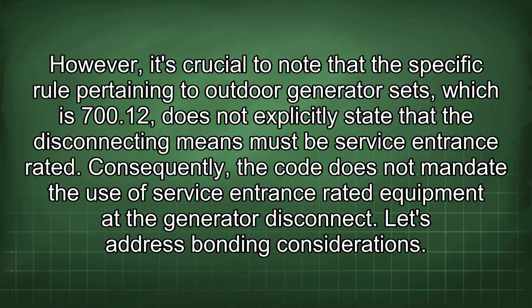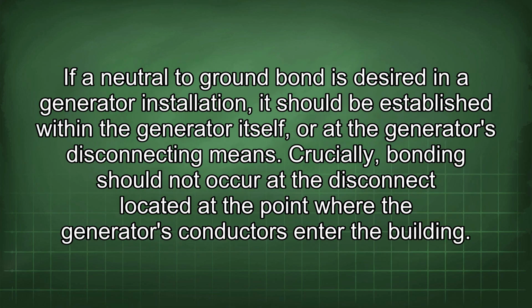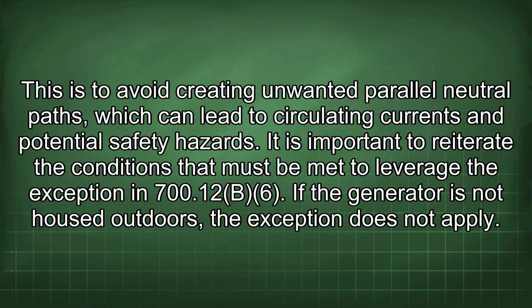Consequently, the code does not mandate the use of service entrance rated equipment at the generator disconnect. Let's address bonding considerations. If a neutral to ground bond is desired in a generator installation, it should be established within the generator itself or at the generator's disconnecting means. Crucially, bonding should not occur at the disconnect located at the point where the generator's conductors enter the building. This is to avoid creating unwanted parallel neutral paths, which can lead to circulating currents and potential safety hazards.